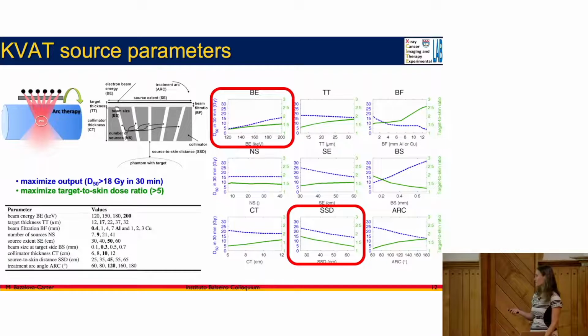The source to skin distance, how far the source is from the patient, had the best performance as well, so we wanted to minimize the source to skin distance. But this is also tricky because you cannot really go too close to the patient. In case the patient moves or shifts to one side, you might end up hitting the patient with the source, and of course this would be horrible. So that shouldn't happen. And the number of sources, or the number of beamlet holes over here, didn't actually matter. So that was just pinpointing some of the conclusions here.